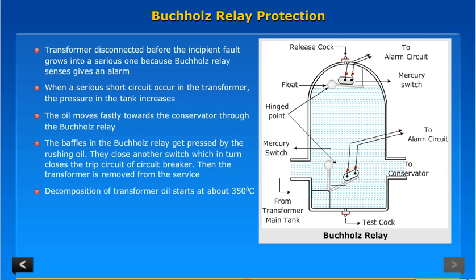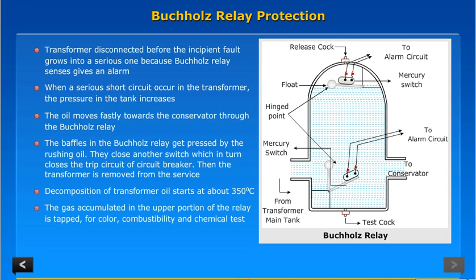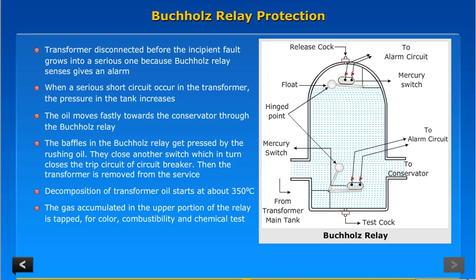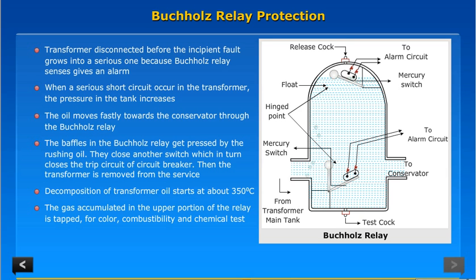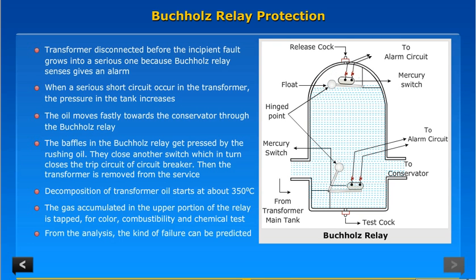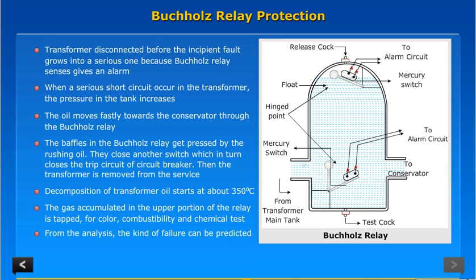Decomposition of transformer oil starts at about 350 degrees centigrade. The gas accumulated in the upper portion of the relay is tested for color, combustibility, and chemical composition. From the analysis, the kind of insulation failure can be predicted.